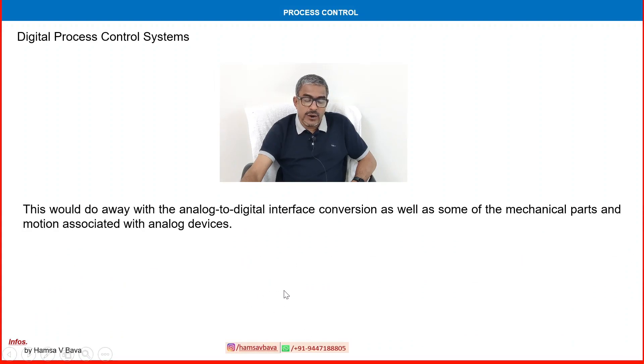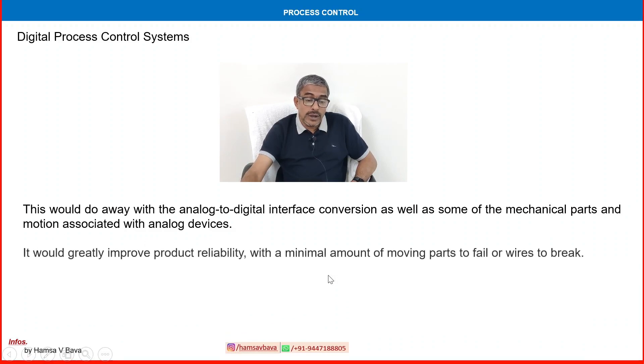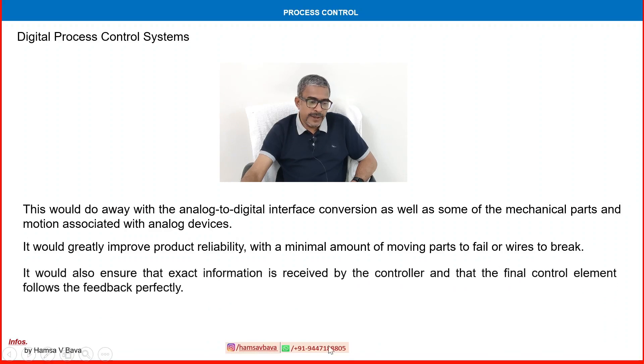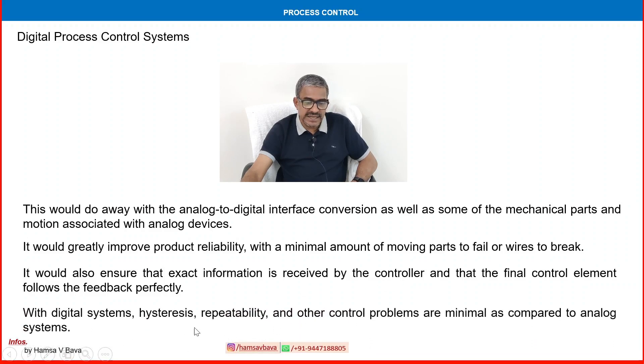This would eliminate the analog-to-digital interface conversion — a major advantage. It would also remove much of the mechanical parts associated with analog devices, greatly improving product reliability with a minimal amount of moving parts to fail or wires to break. Communication received by the controller and final control element would be much clearer and more precise. With a digital system, hysteresis, repeatability, and other control problems are minimal compared to analog systems.